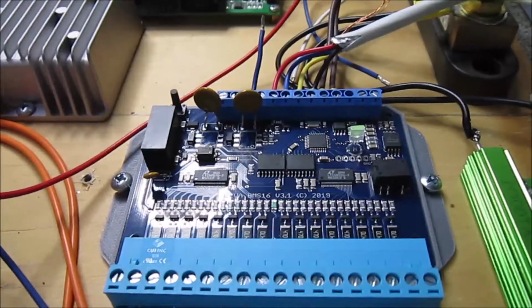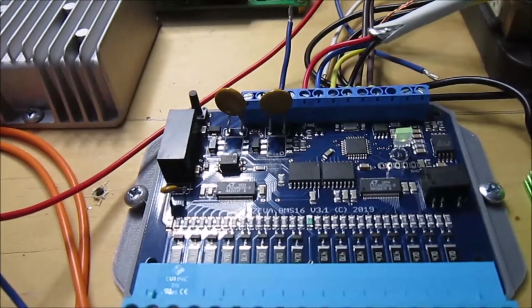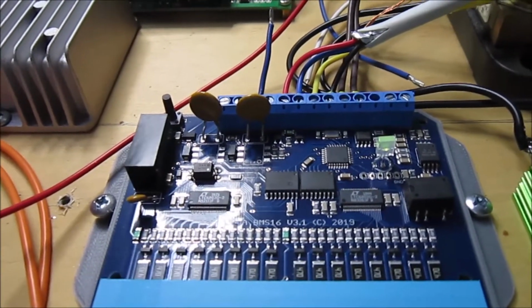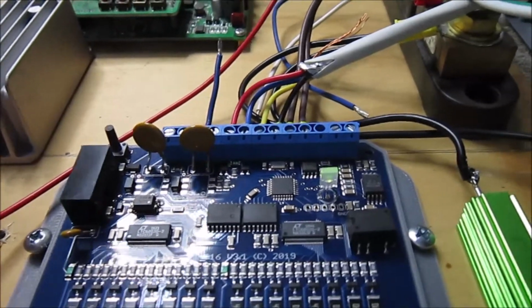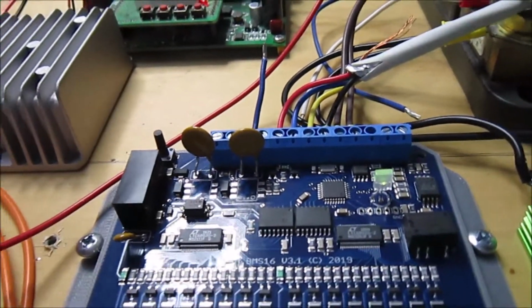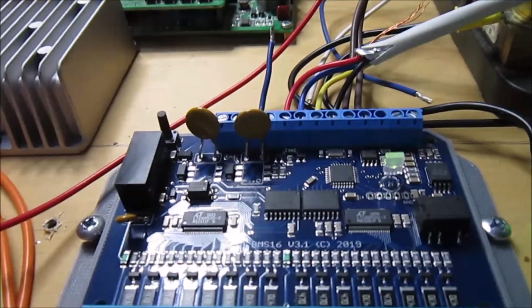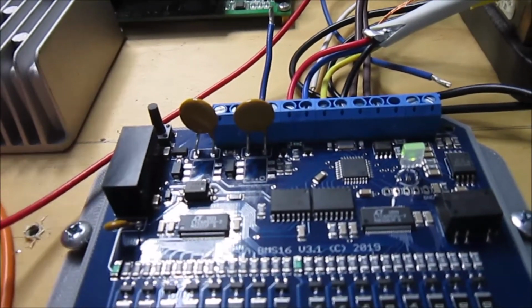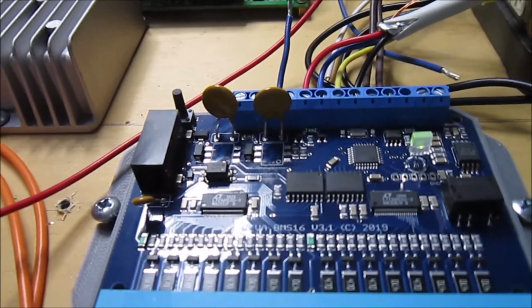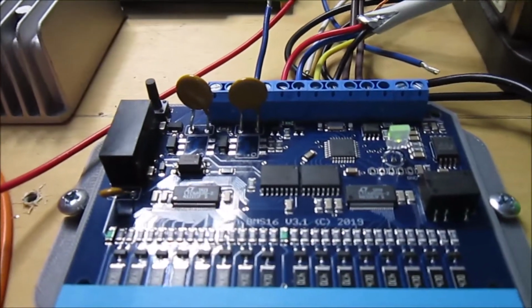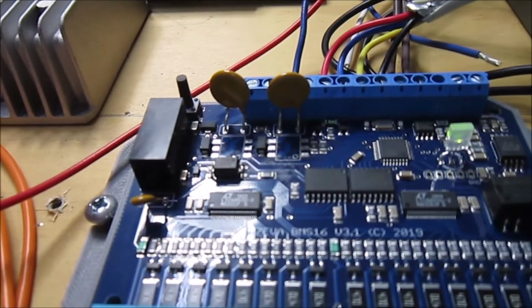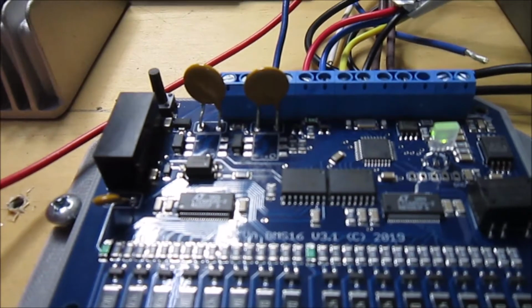Now, I should mention, before the photo relays went bad on this board, I did test remote trip operation, and it worked fine. For anybody who realizes that a mechanical switch and a solid state relay are not exactly the same, any type of semiconductor is always going to have some residual forward current, voltage drop or some leakage voltage. Fortunately, it's not a problem. The voltage does drop low enough when the SSR opened, and it releases this micro relay here, and it does remote trip, so there was no problem.